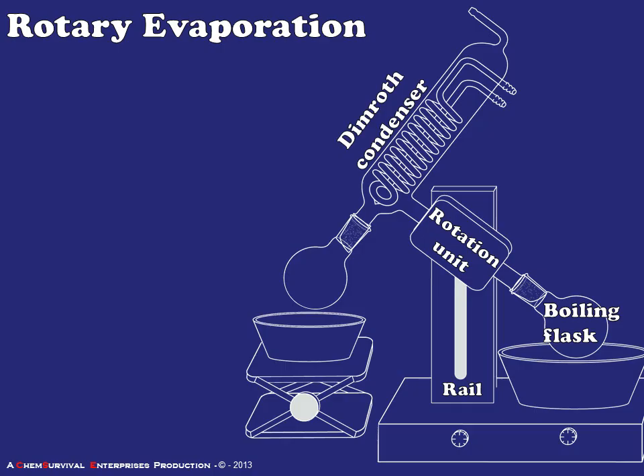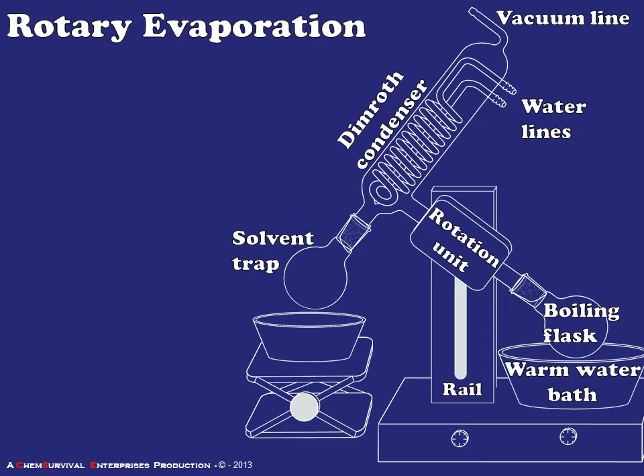There's a Dimroth condenser, which refers to that spiral condenser inside the glassware. That spiral cooling column creates a really large amount of cold surface area, making it a very efficient condenser — and we need that for rotary evaporation to work. There's always a port for attaching a vacuum line and ports for water lines to cool the condenser. What would be the receiving flask in a distillation is here referred to as the solvent trap, implying we're catching the solvent away from the residual non-volatile material in the boiling flask. There's a warm water bath to encourage evaporation in the boiling flask, an ice bath to discourage evaporation once solvent has begun accumulating in the trap, and controls for rotation and temperature.